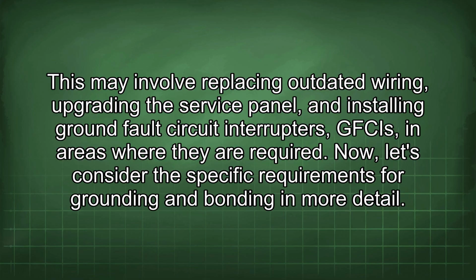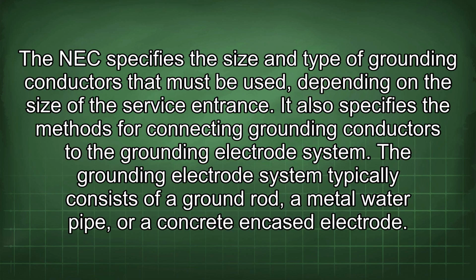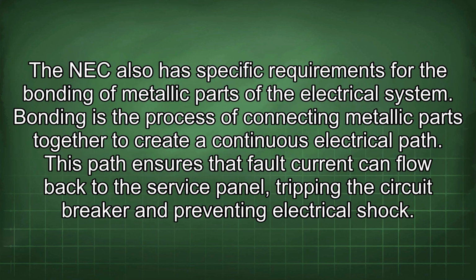Now let's consider the specific requirements for grounding and bonding in more detail. The NEC specifies the size and type of grounding conductors that must be used, depending on the size of the service entrance. It also specifies the methods for connecting grounding conductors to the grounding electrode system. The grounding electrode system typically consists of a ground rod, a metal water pipe, or a concrete encased electrode. The NEC also has specific requirements for the bonding of metallic parts of the electrical system.